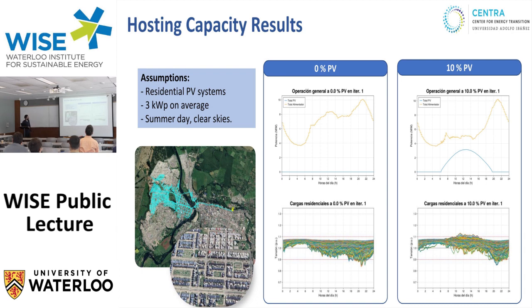This is the kind of result the model offers. We take the basic load profile, knowing the measurement of the load profile at the substation, but we don't have information downstream. So we start feeding load profiles to the feeder until we match the measurement at the substation.